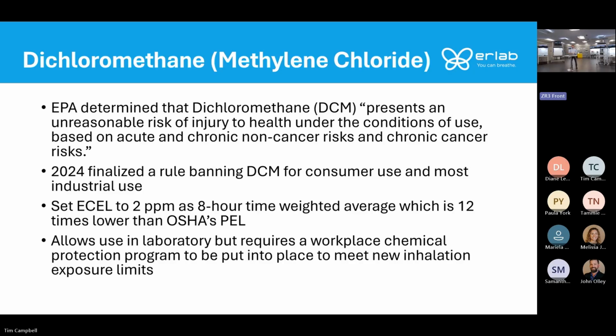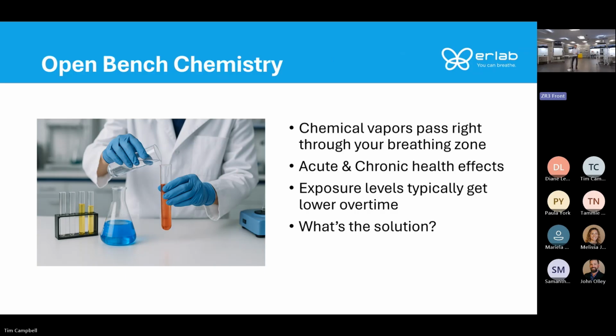They do still allow it in laboratory use, but starting last summer in 2025, they said if you were going to use it, you had to keep the exposure below 2 parts per million as an 8-hour time-weighted average, which is 12 times lower than OSHA's PEL. But you'd also have to put a workplace chemical protection program into place to protect the workers when they are working with dichloromethane. Last summer, we had an influx of inquiries for our ductless fume hoods because people were using dichloromethane for open bench chemistry.